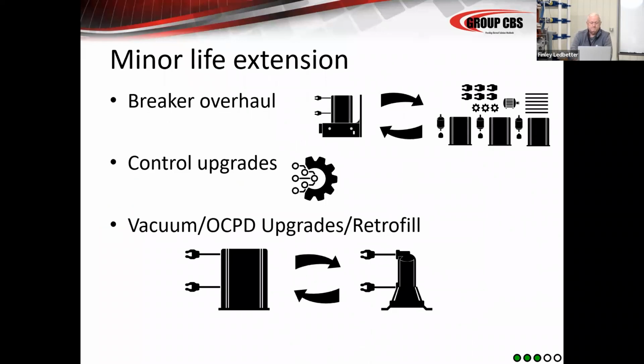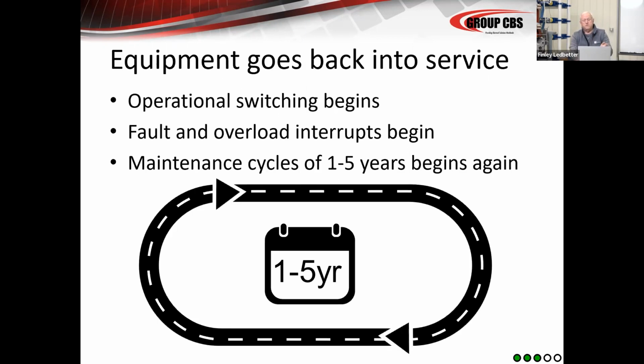So when we go through it the next time, we have to talk about some possible minor life extensions, possibly breaker overhauls between 25 and 50 years. Possibly there's some control upgrades, new relaying, new control transformers, CTs, PTs, things that you want to do. Maybe you want to upgrade or retrofill the overcurrent protective devices, change some of that sort of thing. So between the first and second life cycle, there is some minor life extension things you may want to consider. And there again, the paper deals with that, and we'll talk about that in detail later. Just believe me, there are. The equipment goes back into service, and you see these 5-year cycles again, by which you do similar testing, similar inspections every 3 to 5 years for the next 25 years.